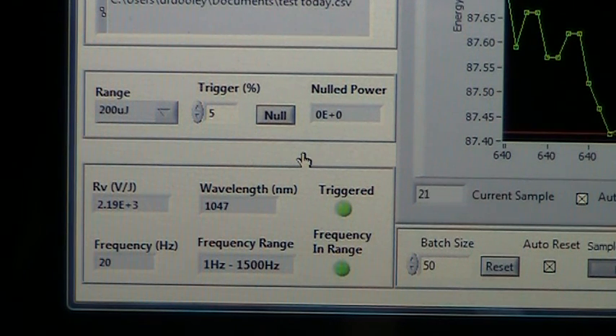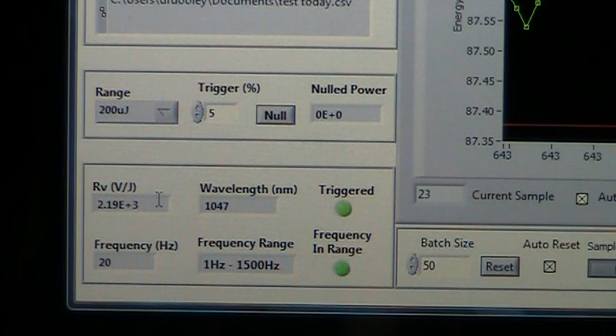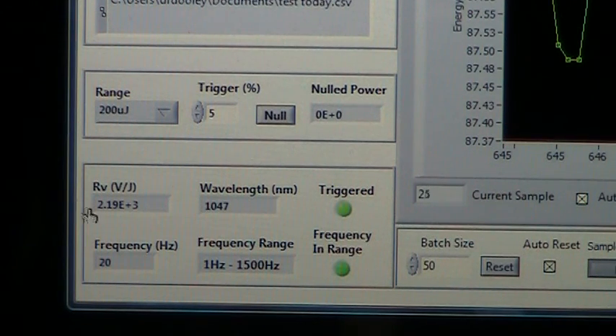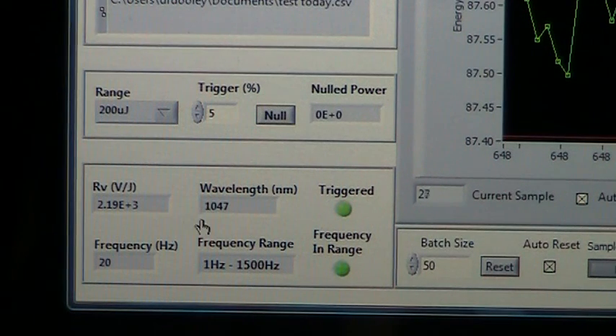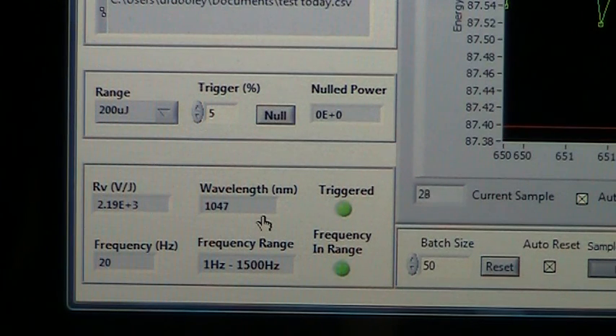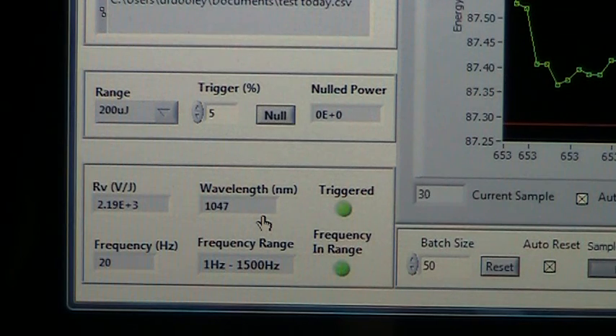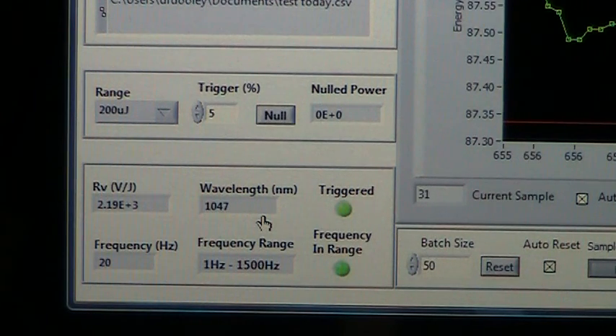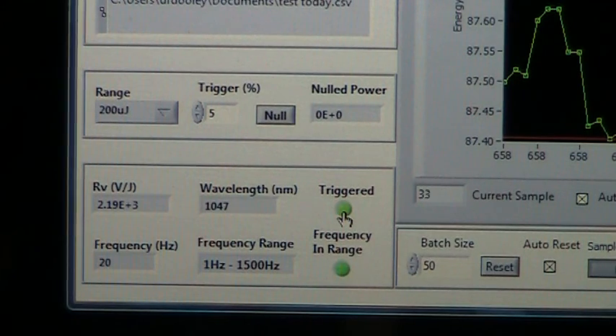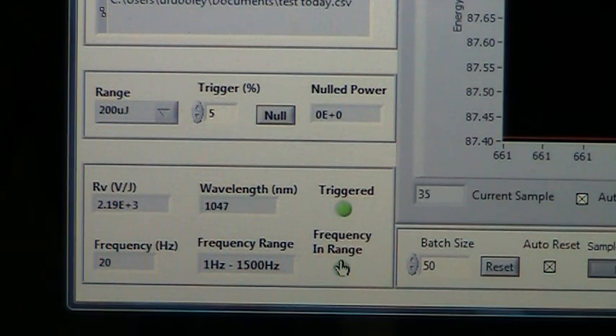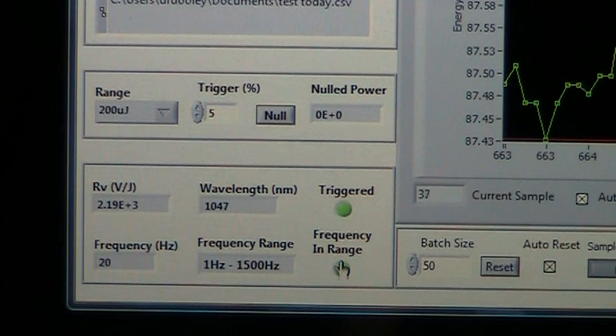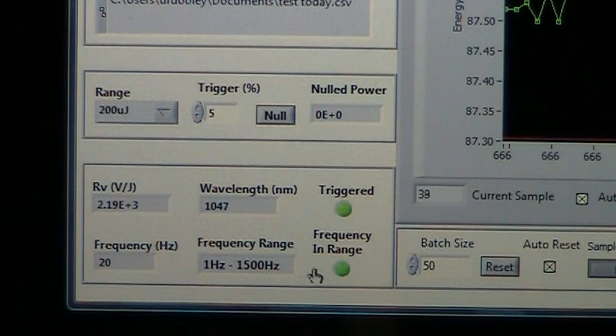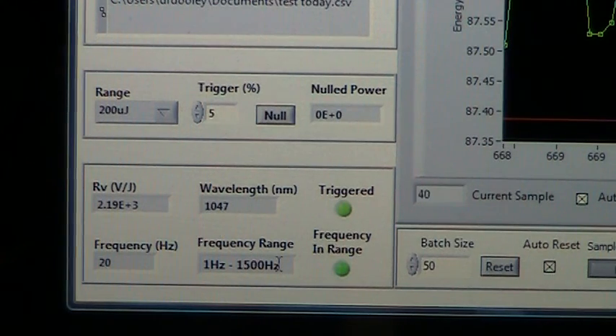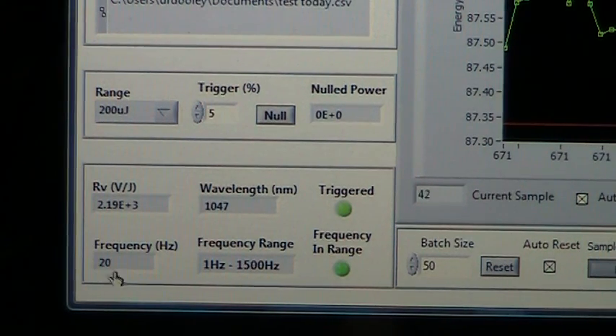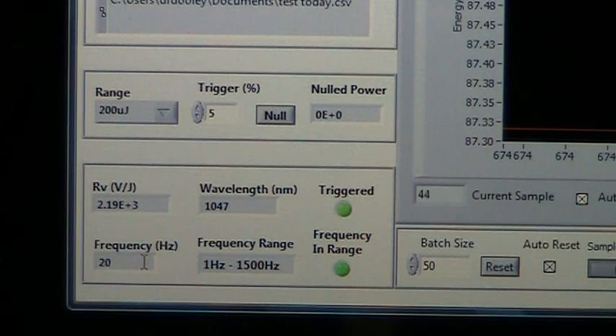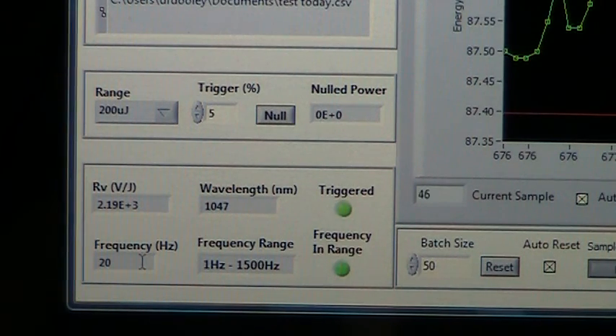Moving down in the lower part of the display, there are status annunciators here. There's a window that displays the RV of the probe in volts per joule. There's a wavelength window that displays the wavelength that we were measuring at, which is in nanometers, 1047. There's a trigger annunciator, which should be green if it's triggering properly. Just below that, there's a frequency in range annunciator, which should also be green. It means that we're within the 1 to 1500 hertz frequency range capability of this instrument. In the lower left-hand corner is a window that shows the actual frequency that the laser is running at. Right now, that's 20 hertz.